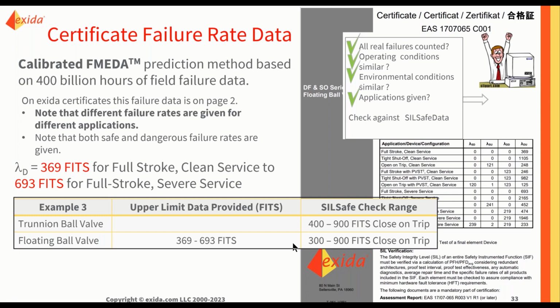The best is, what's the best on here? Full stroke clean service. Yeah, I guess that makes sense. Clean service does not cause as many failures as severe service. Full stroke close on trip is a very common application. This data is credible.